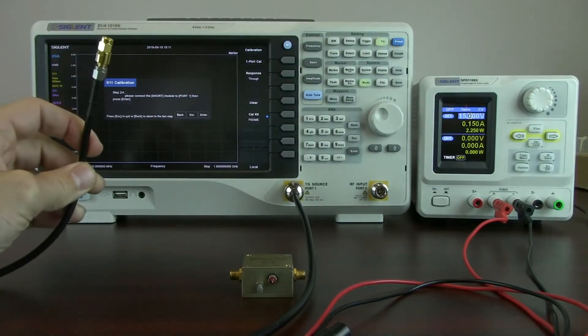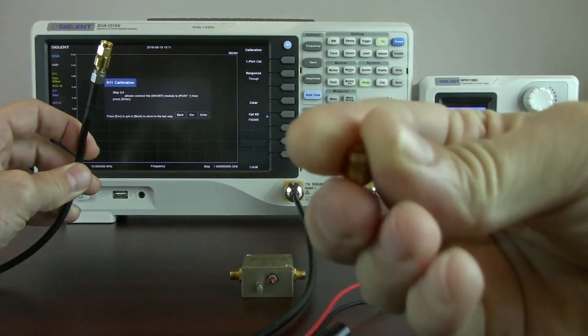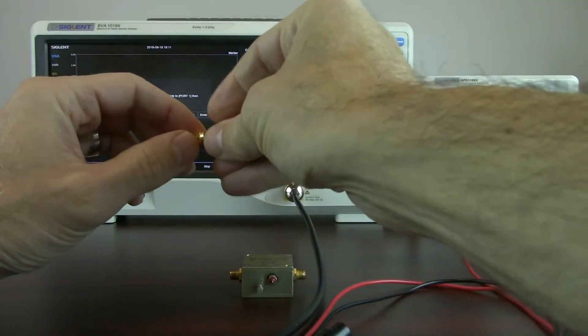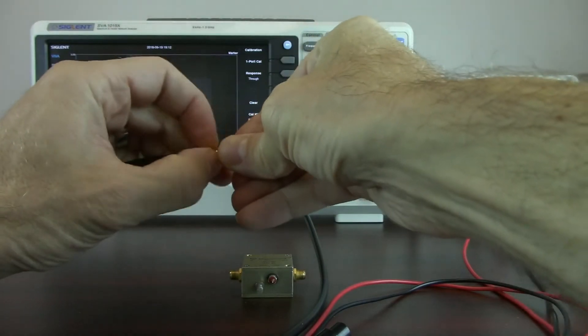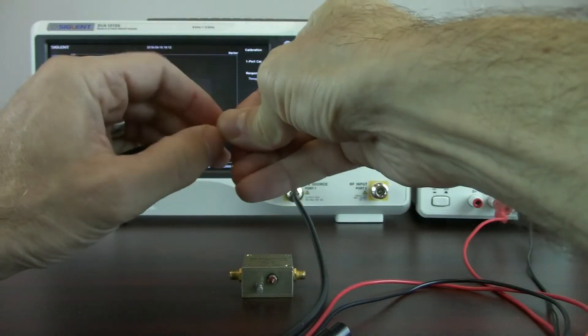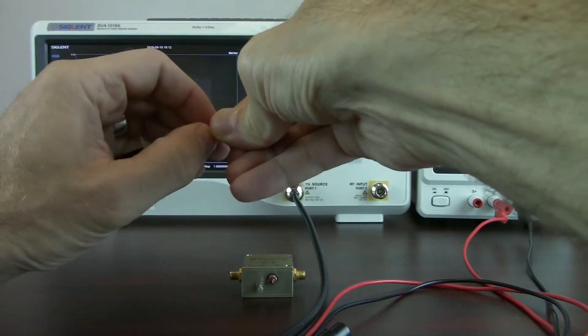Now it says to short. So I've purchased and already characterized this SMA short. Again, I'm holding the short and I'm rotating the hex connection here for the adapter.